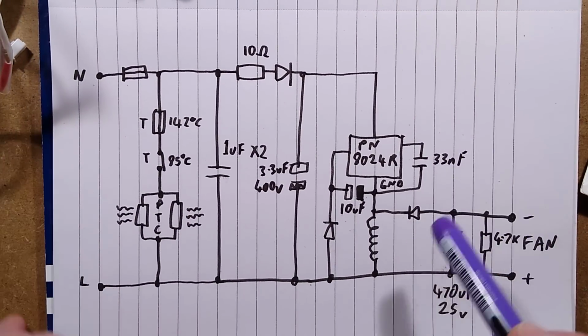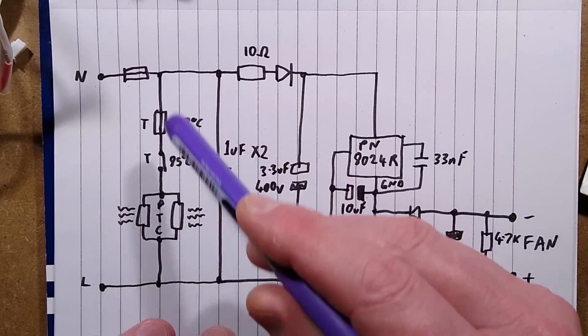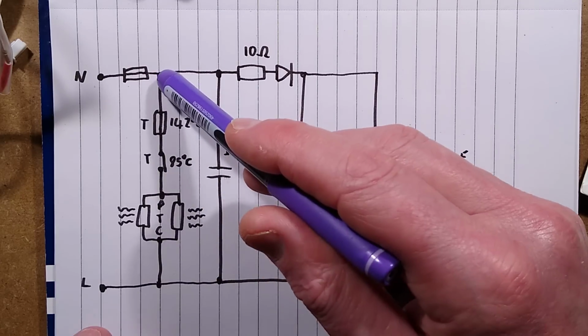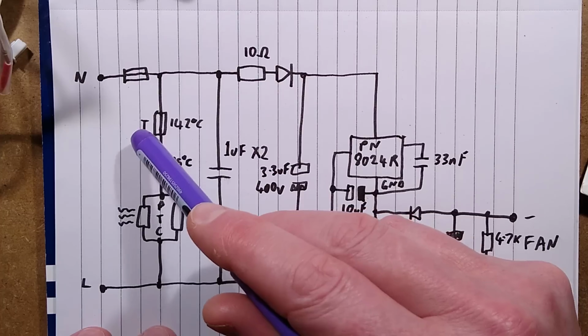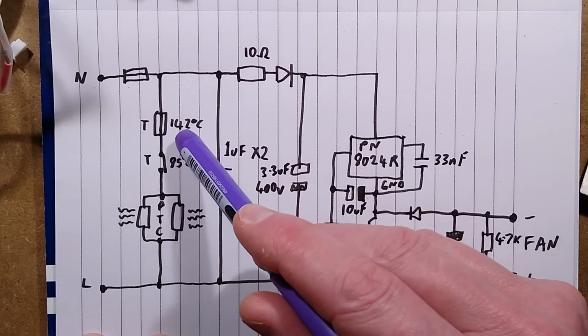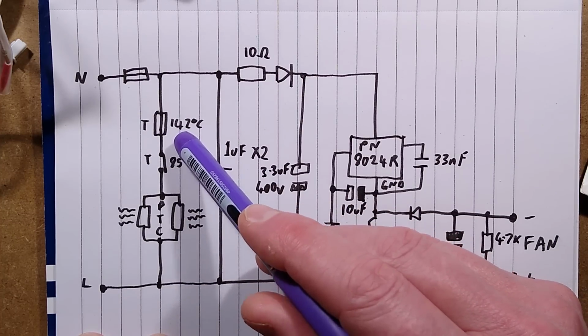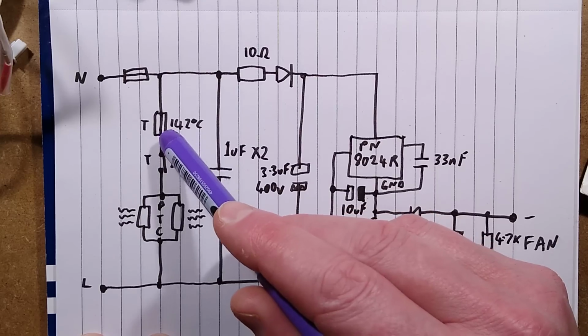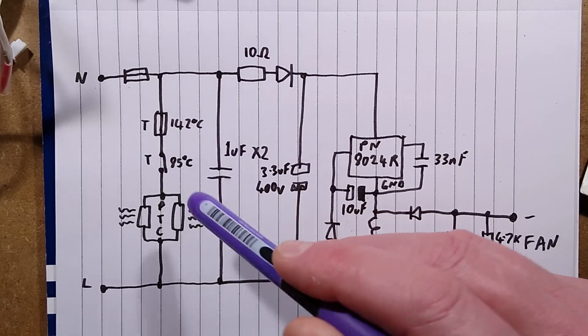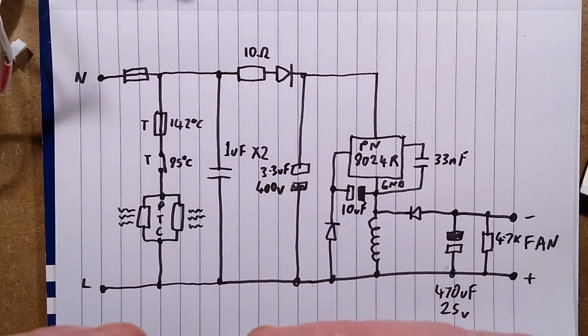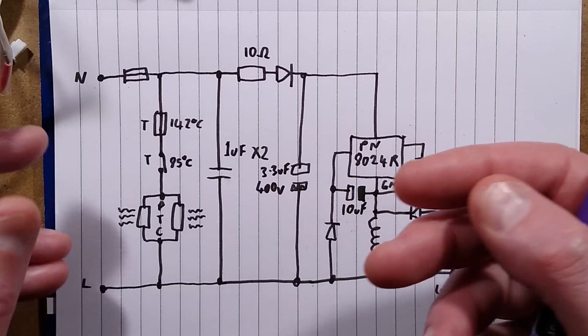So here is the circuitry. Neutral comes in, goes through the fuse, and then it feeds the heaters directly by going through the thermal fuse. There's the one-shot thermal fuse, the worst case, the one that trips when everything else has gone wrong. It's set to 142 degrees Celsius. If it gets that high, it's the last resort, kill the unit, and the unit will not work after that.